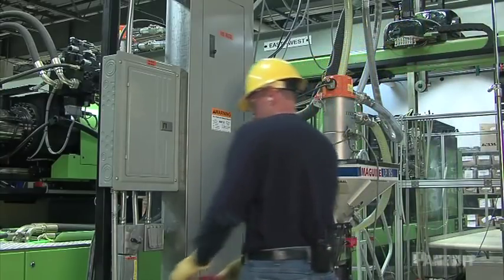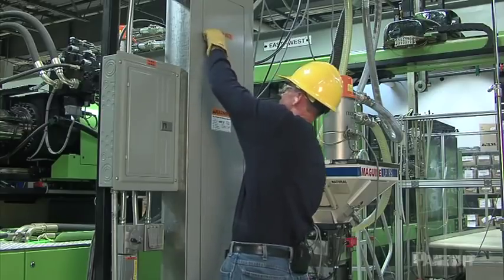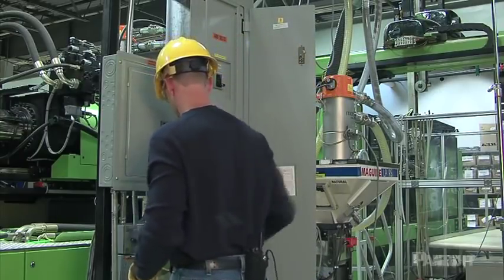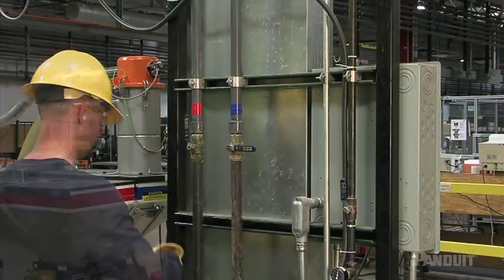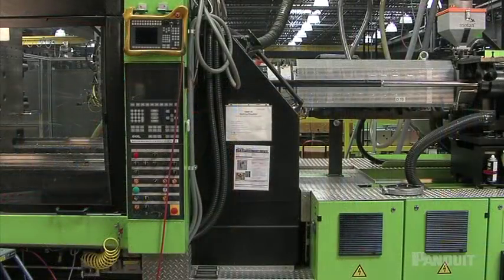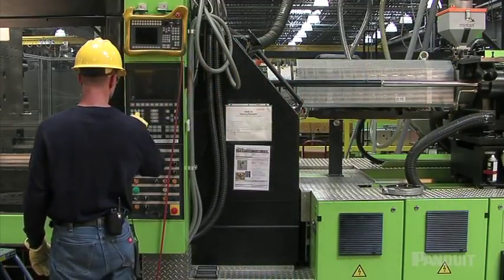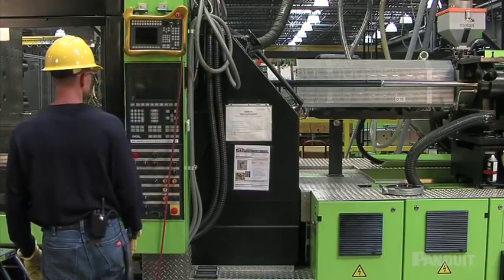Do not rely on just the push button or on-off switch. Always disconnect the energy source after turning the machine off. If you disconnect the machine under load, you risk damaging the equipment. Take the time to make sure you have isolated the equipment from all energy sources, as many machines have more than one source of power. After turning off the equipment and isolating it from the power source, test to make sure the equipment is isolated by trying the on-off controls or using test instruments.